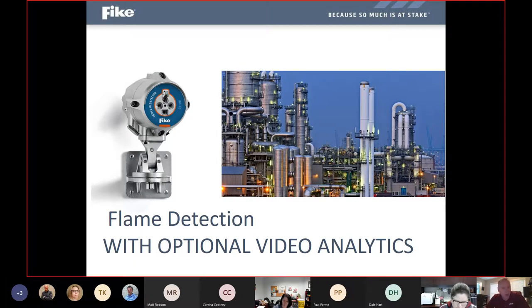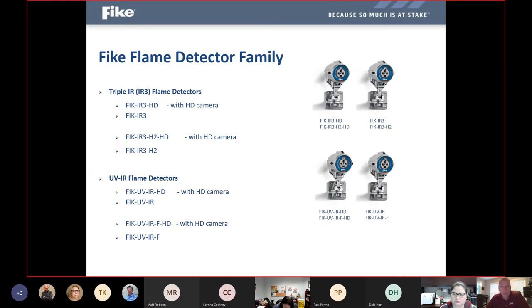The flame detectors are a listed fire detection system, and Fike has a great product line of triple IR and UVIR flame detectors that are used in some very heavily industrial and big wide open applications and areas as well, because of their immunity to false alarms and their quickness to be able to respond to an actual fire event in any given area.